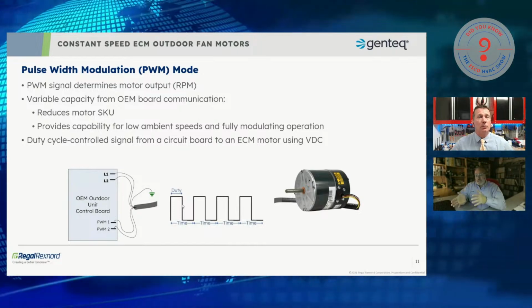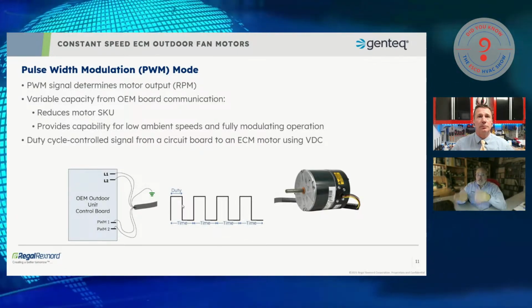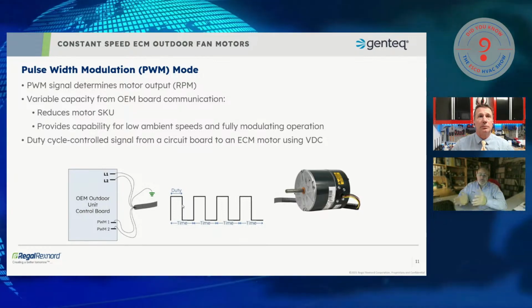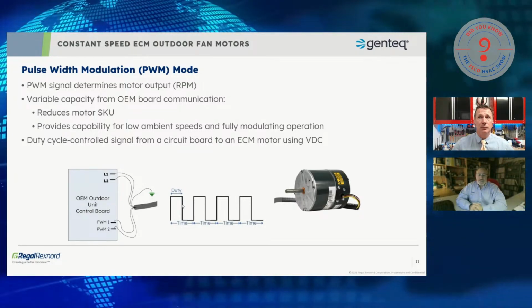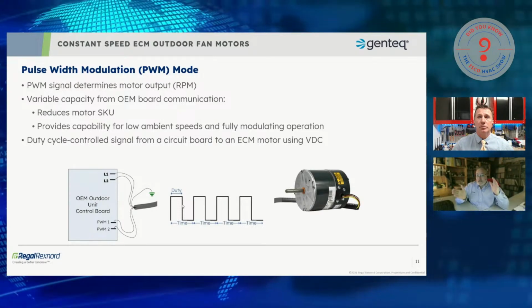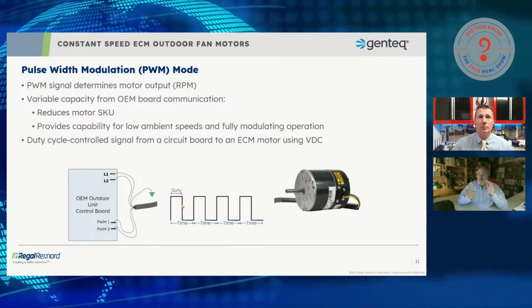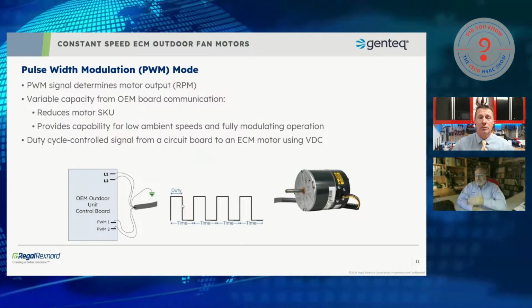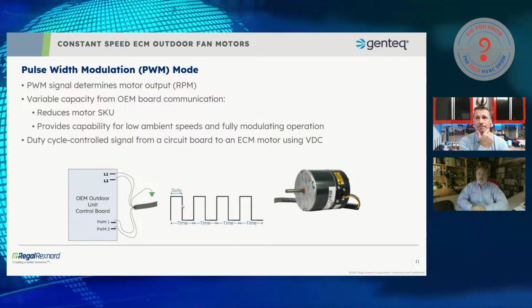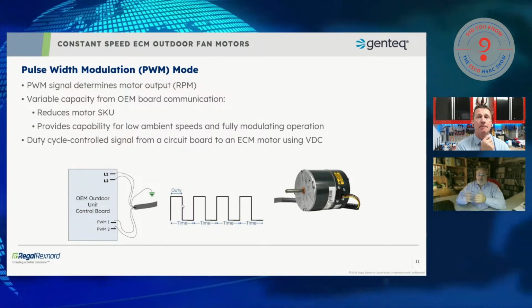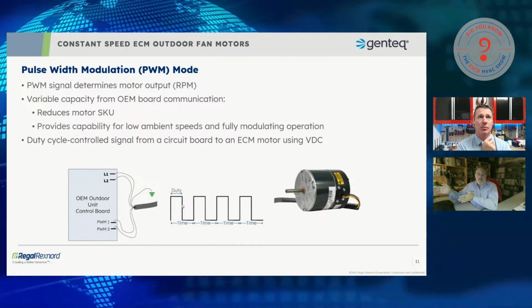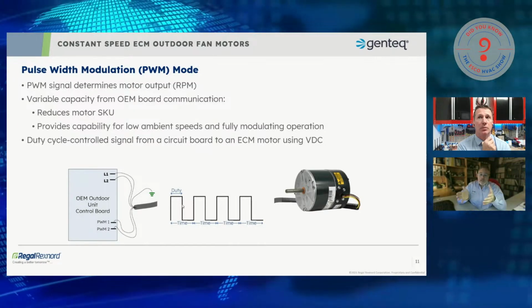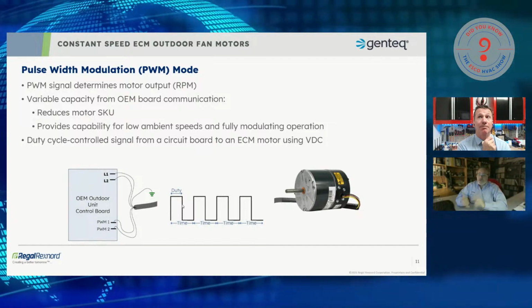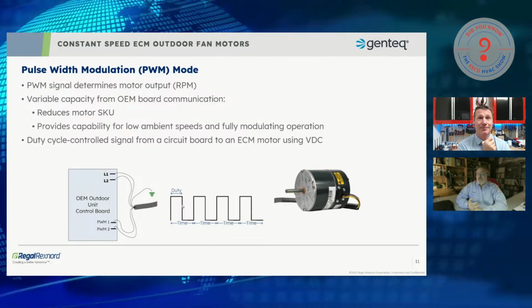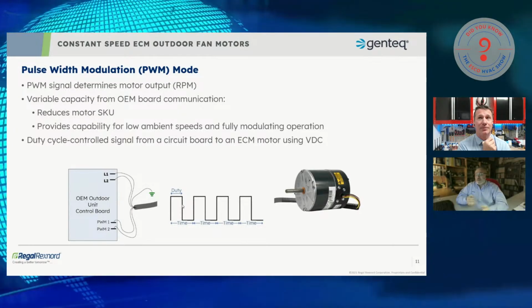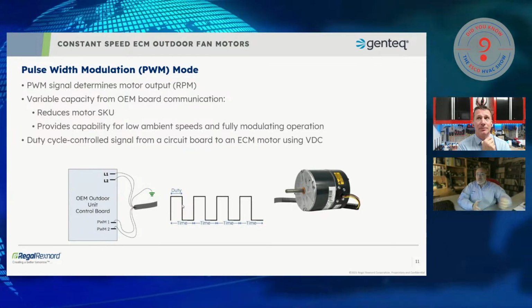So in PWM, the manufacturer doesn't have to program each motor and each motor speed individually for each unit. Really, all they program into the motor is the min-max value. So they can leave it wide open to the 600 to 1,200. They can skinny it up to 600 to 1,000. But whatever that min-max is, then the PWM signal, in this case a 50% duty cycle, is going to be based on that min-max. So using all of that information as the example, the manufacturer can put all the programming in their board, and the motor SKU and the motor programming can stay the same from one unit to the next. So it reduces the SKUs the motor manufacturer has to use. It increases the programming flexibility because it's all back in their board. They don't have to program each motor as it comes down the line.